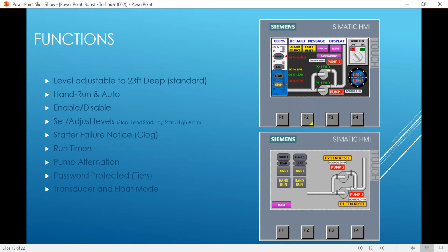It also gives the plumber a lot of easy conveniences. For instance, on your top screen you can see it's got your alarm and your fault reset. It shows you pump 1 or pump 2. And by the way, one of the neat things is that it actually tells you which pump is bad. So if you have to open the pit, it will tell you, hey, it's pump 1. You don't have to dig down there, pull out both pumps and look at them both. You know exactly which one is in fault.